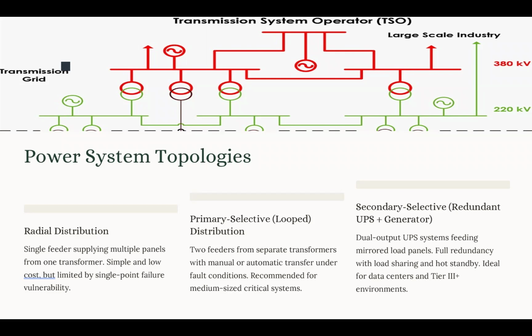Now, the next choice for the topology of the power system is the primary selective distribution, or as we call it, looped distribution. So in this topology, we have two independent feeders, each from a separate transformer or power source, which is arranged in a loop configuration. Manual or automatic transfer switches basically enable alternate power routing during a fault. So basically, one source can fail while the other maintains the service. That switching between them can be manual or automatic based on the criticality of the system. It is normally used in a medium-sized critical system like hospitals or university laboratories or manufacturing with moderate downtime tolerance.